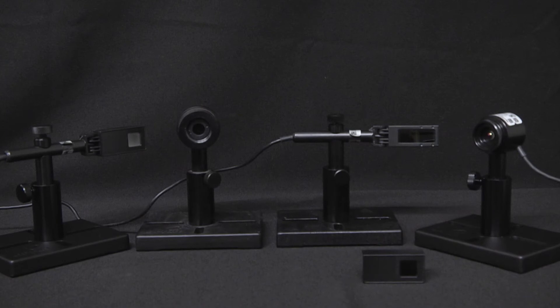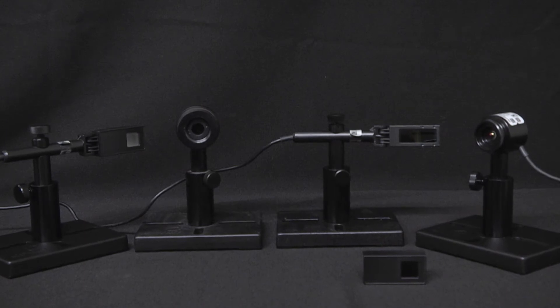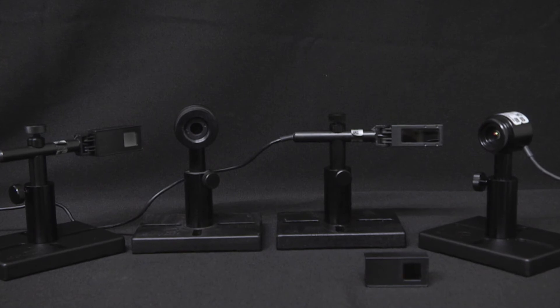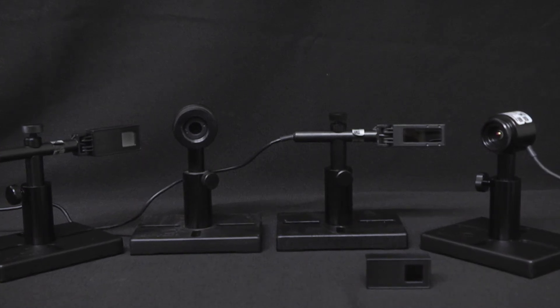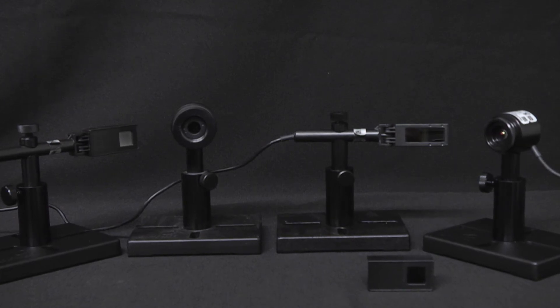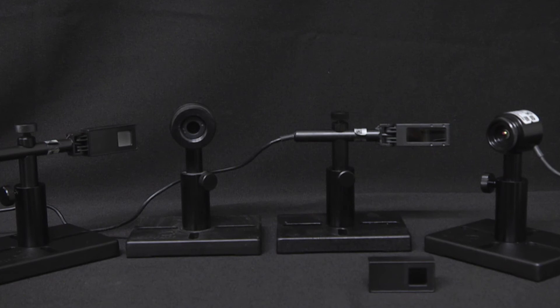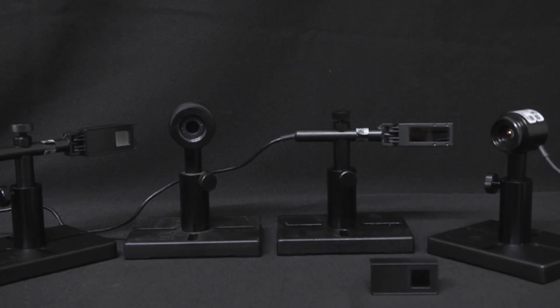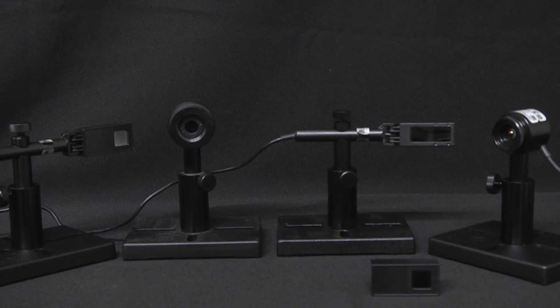For very low powers, from picowatts up to several hundred milliwatts, we normally use photodiode sensors. These are based on semiconductor detector elements, where light is converted directly to electrical current, which is then measured. Ophir offers several types for different spectral regions and different power levels.